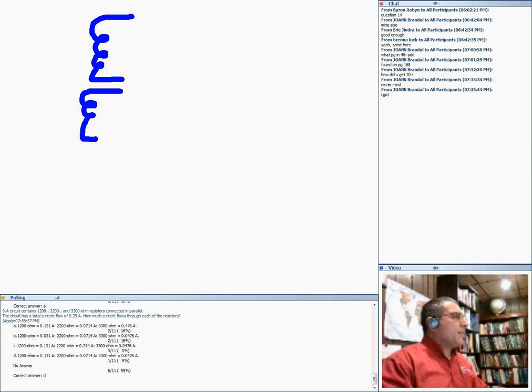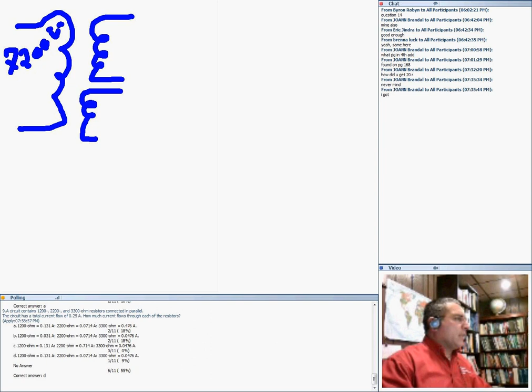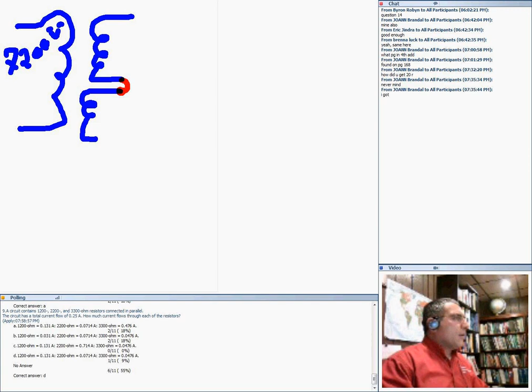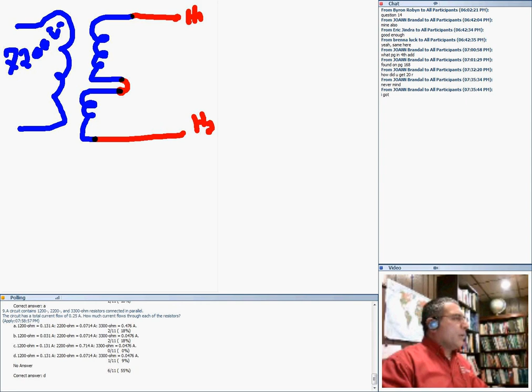On the other side of the transformer, the high voltage side, say 7200 volts, is the utility side. On this side is the typical setup we give to residential. They tie these two together, center tap they call it, and here's your hot one, and on the other side, hot two. Up to this point, no problem. This coil is rated for 120 volts, and this coil is also rated for 120 volts, right?